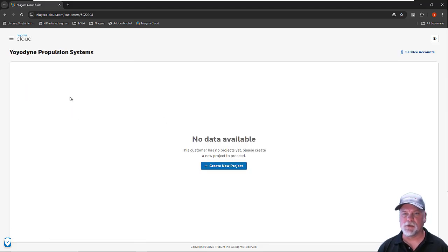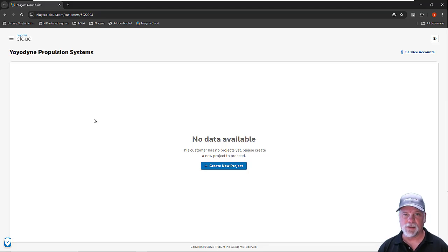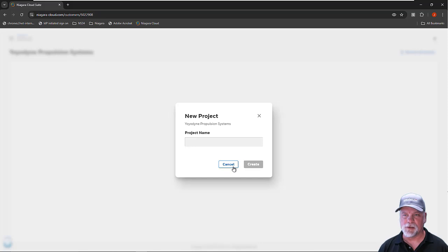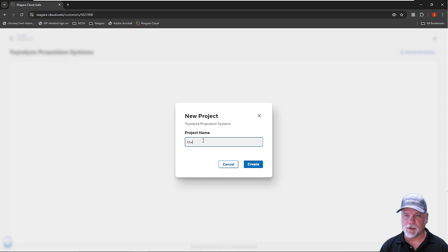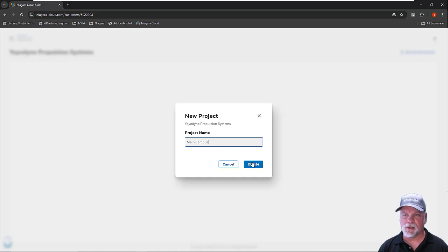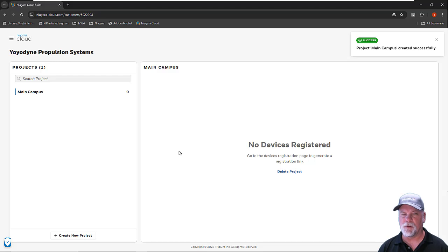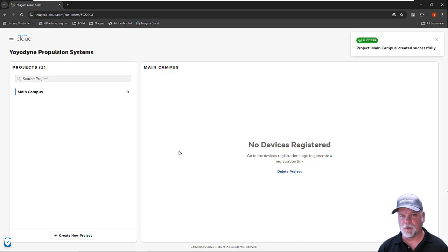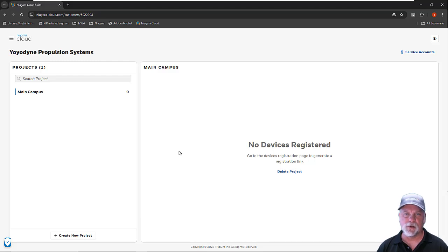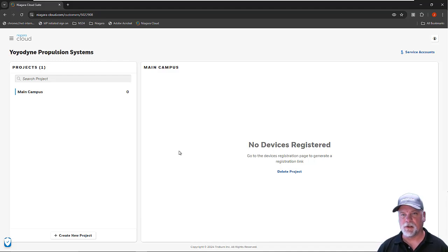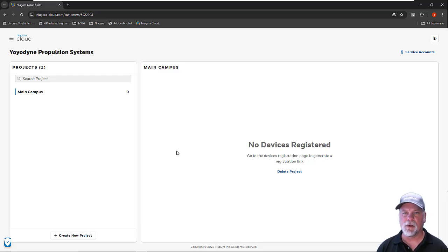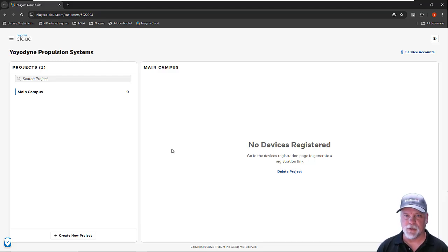If I click on the customer, I'll see an indication that there are no projects set up, and it's trying to get me to create a new project. You have to create at least one, but you can have more than one project for each customer. The idea with projects is that it's a folder or a container to group Niagara hosts under. If you wanted to control access to certain sites for certain users, you can create groupings with those projects, and when you register the devices, you're able to put them under specific projects. It really helps with managing access to those user accounts.